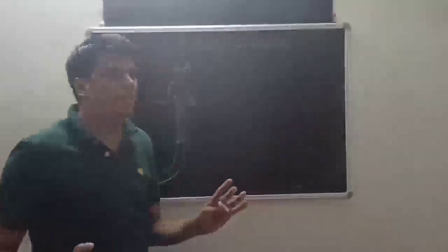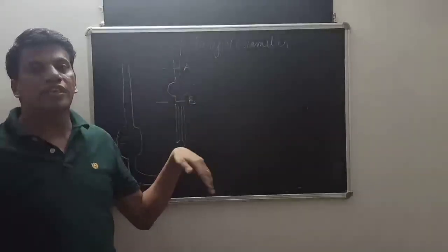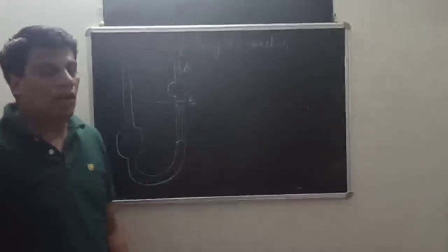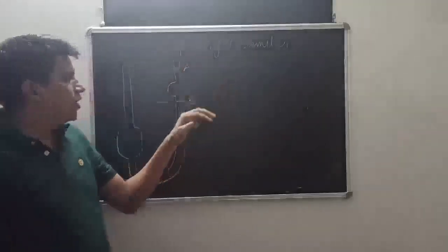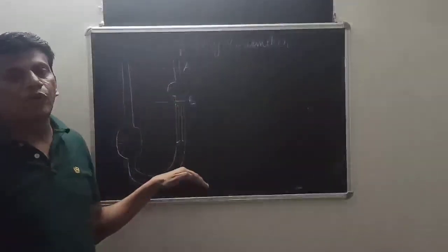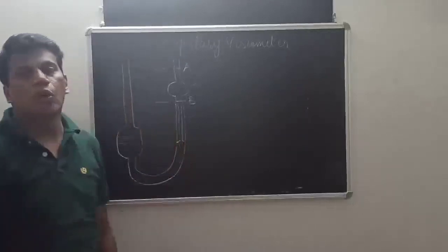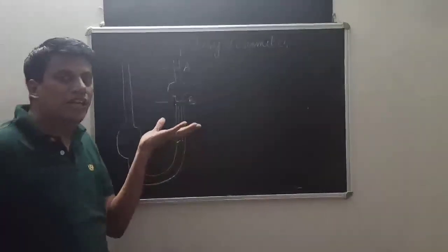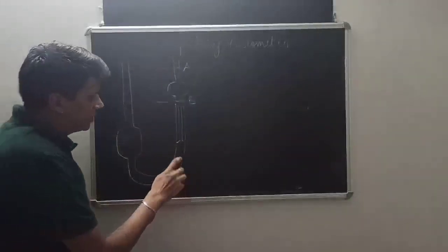Now we come to the second type, or modified form, of Ostwald viscometer. Same principle, everything is the same. Just one drawback of capillary viscometers, or Ostwald viscometers, is overcome by the Ubbelohde viscometer. Poiseuille's equation says that liquid is freely moving through a capillary. When it is freely moving through a capillary, there should be no liquid beneath the capillary. But in the Ostwald viscometer, there is a liquid beneath the capillary which slightly changes the result.